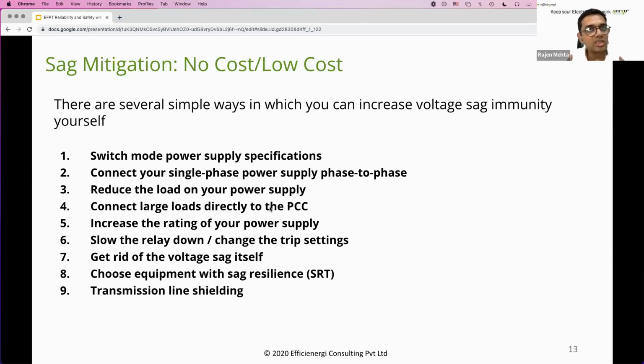where you have a strong grid available. The fault level is much stronger, and the voltage sag caused by the operation of such large loads will not have a significant impact on the other loads within your facility. Or you can choose equipment with sag resilience. Sag ride-through is one of the considerations you should have while selecting equipment during the design stage. While you are going to buy or replace equipment, ensure that the vendor complies with the SEMI F47 standard, which is typically the standard looked upon for semiconductor-driven equipment to be able to ride through a certain voltage sag.